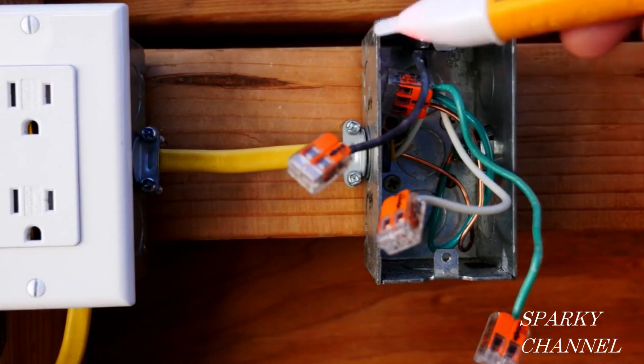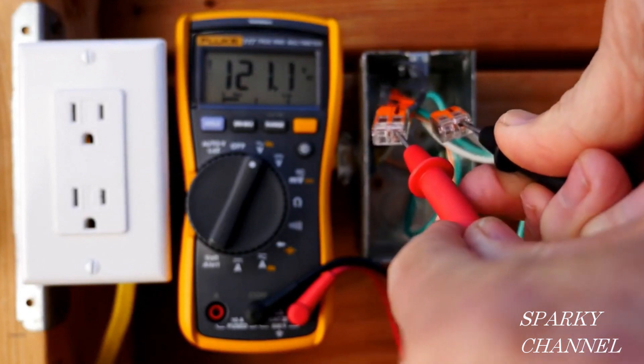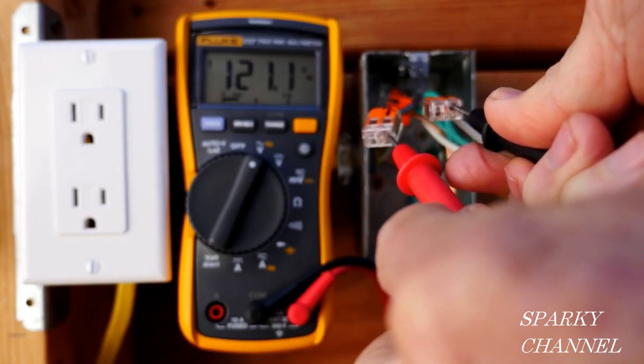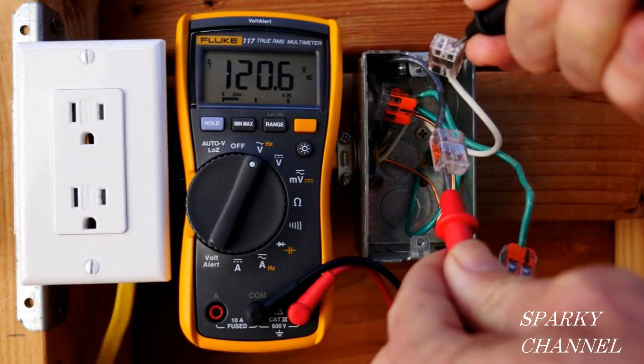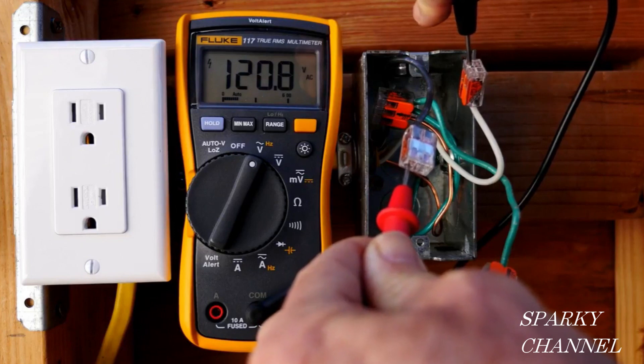So the black is the hot. Whenever you're working on a receptacle it's always a good idea to test and see what kind of voltage you're getting. Here I'm reading 121 volts AC and I'm using my leads in the ports of the Wago lever nuts — that's a good safe way to do it.